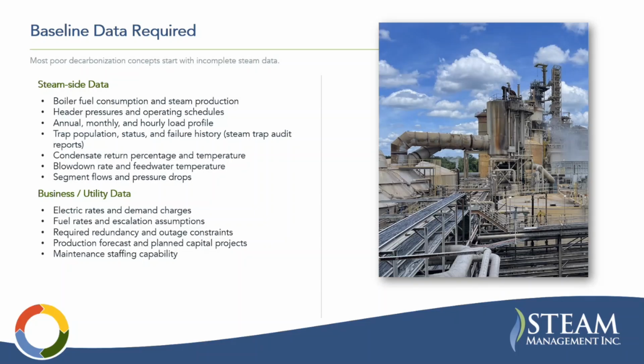Baseline data required when you're doing an assessment. So far as steam side, look for boiler fuel consumption and steam production, header pressures and operating schedules. Annual, monthly, and hourly load profiles or trend data can give you a lot of this information. Trap population status and failure history, like a steam trap audit report, is a really good indicator of a lot of characteristics of a steam system. Condensate return percentage and temperature, blowdown rates and feed water temperatures, segment flows and pressure drops are some of the key data points that are helpful.